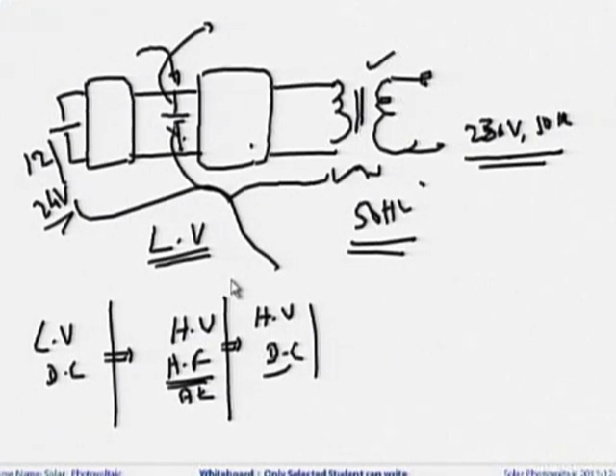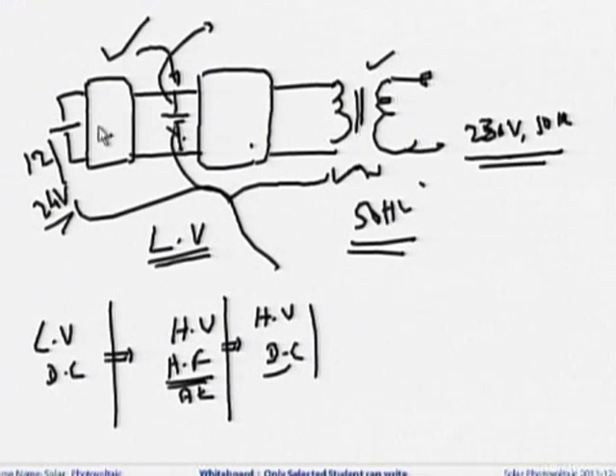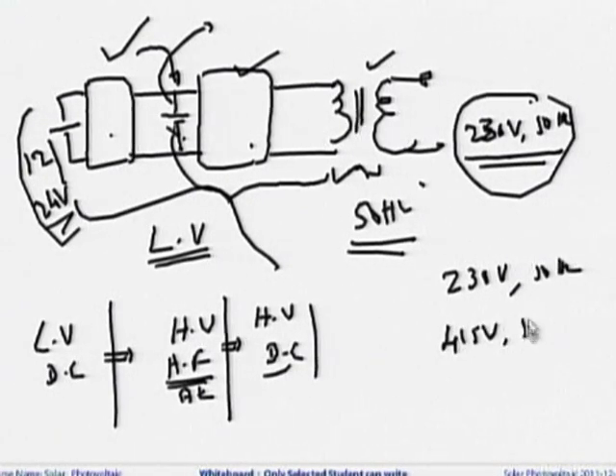If you want a purely sinusoidal supply, I may have to use an LC filter at the output of the inverter. If isolation is required, I can use a 50 hertz one-to-one transformer. So the entire configuration changes depending on the requirement and application. So far we discussed the DC to DC conversion block and the DC to AC conversion block, giving either single phase 230 volts 50 hertz or 415 volts 50 hertz AC.